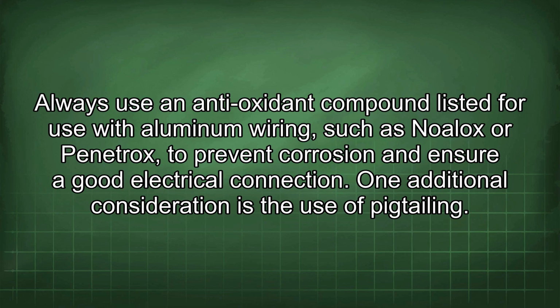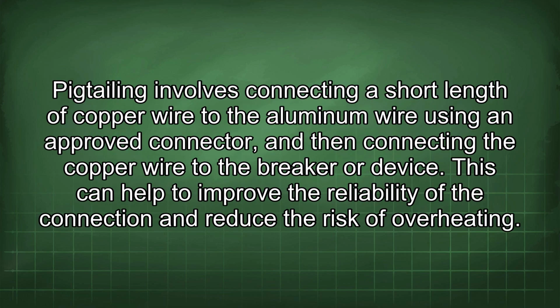One additional consideration is the use of pigtailing. Pigtailing involves connecting a short length of copper wire to the aluminum wire using an approved connector, and then connecting the copper wire to the breaker or device. This can help to improve the reliability of the connection and reduce the risk of overheating.